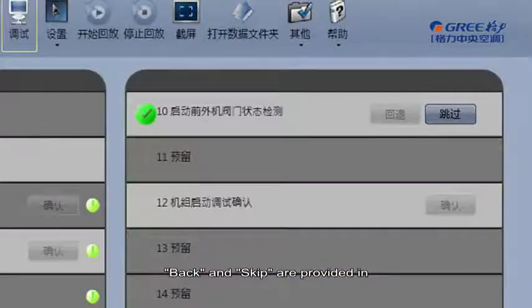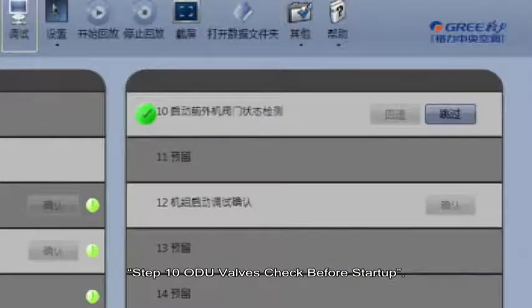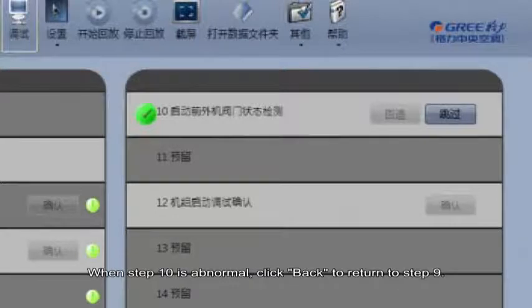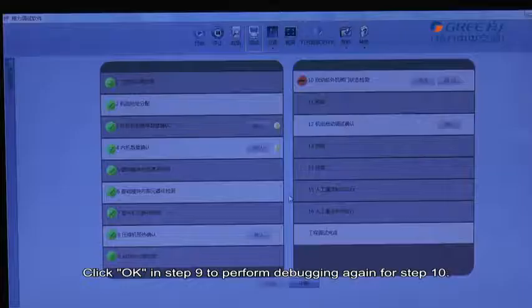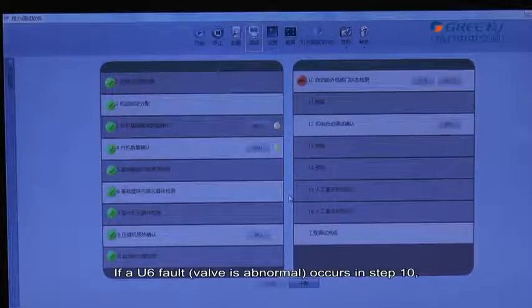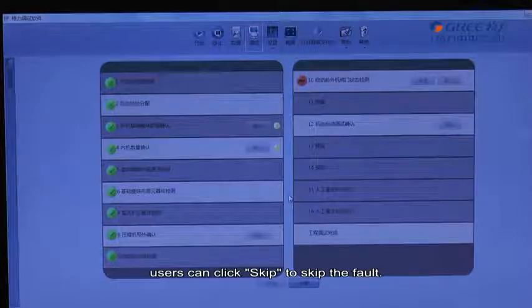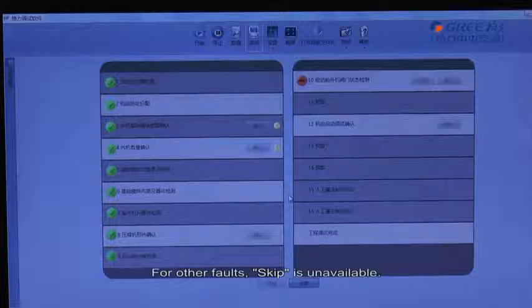Back and skip are provided in Step 10, outdoor unit valves checked before startup. When Step 10 is abnormal, click back to return to Step 9. Click OK in Step 9 to perform debugging again for Step 10. If a U6 fault occurs in Step 10, users can click Skip to skip the fault. For other faults, skip is unavailable.